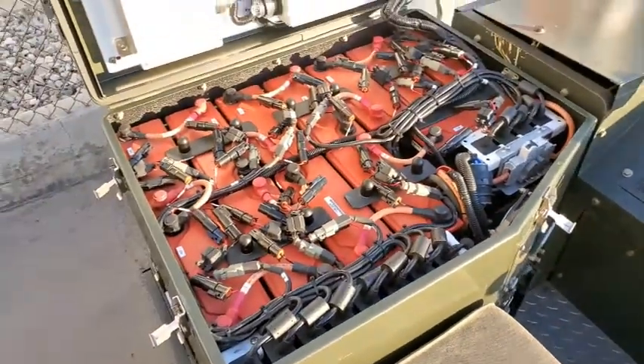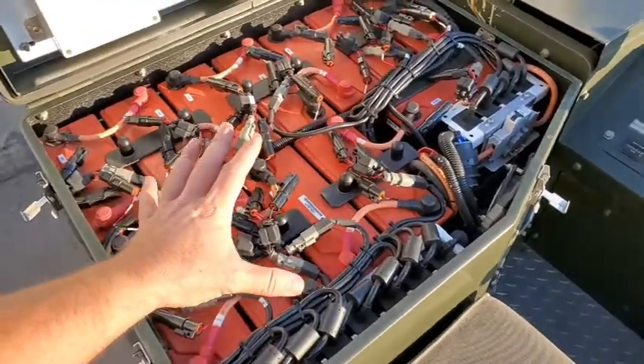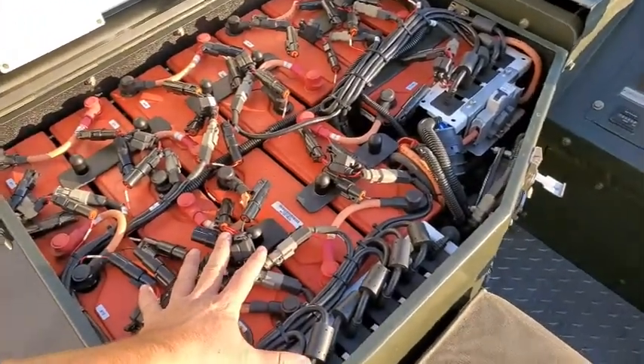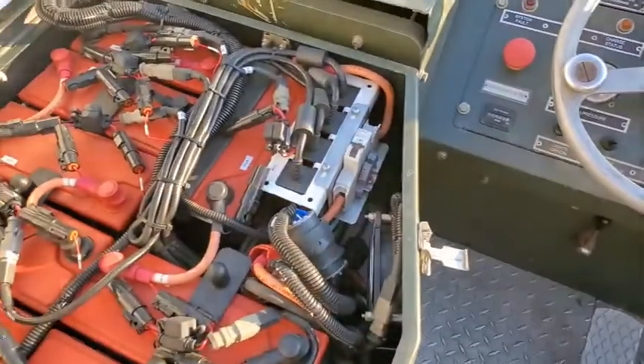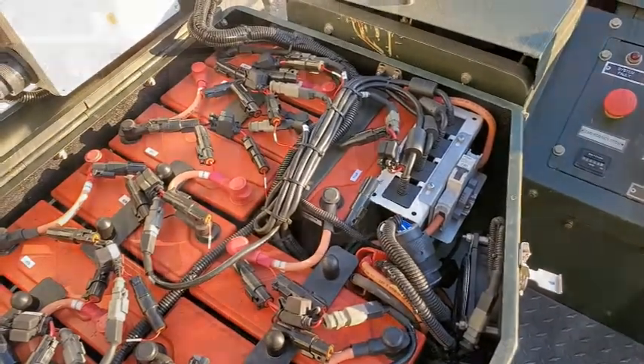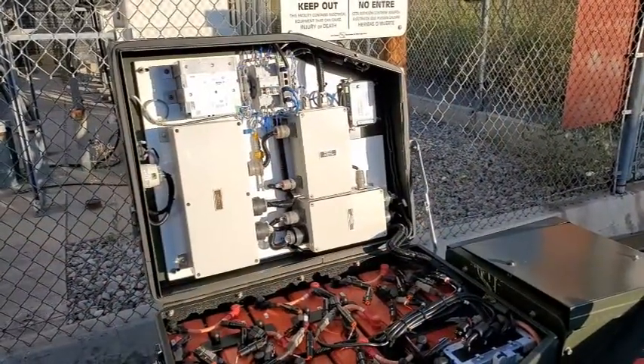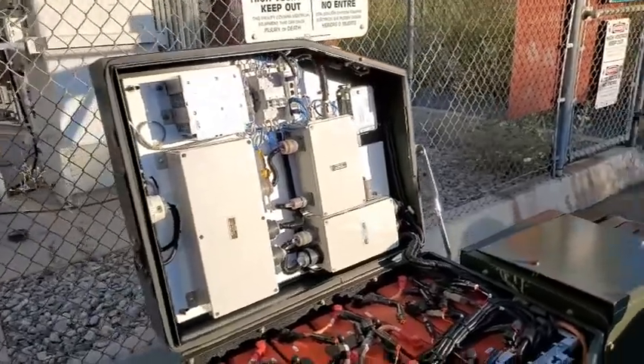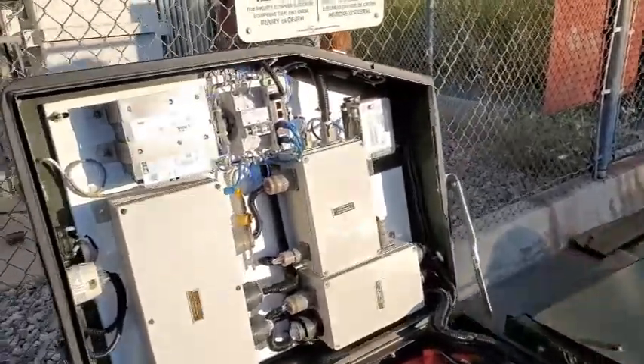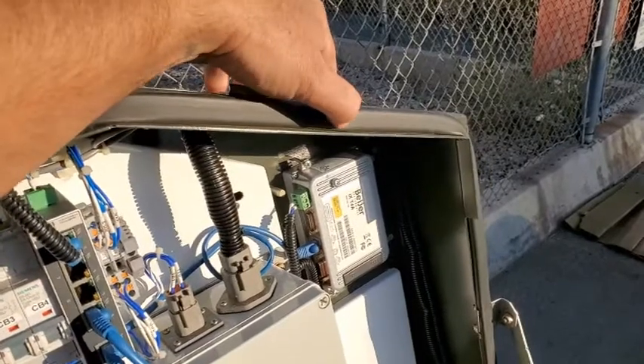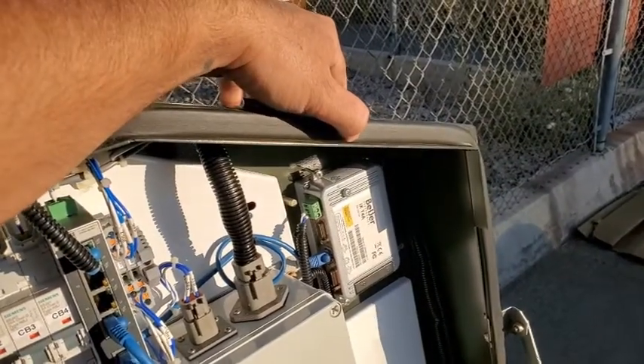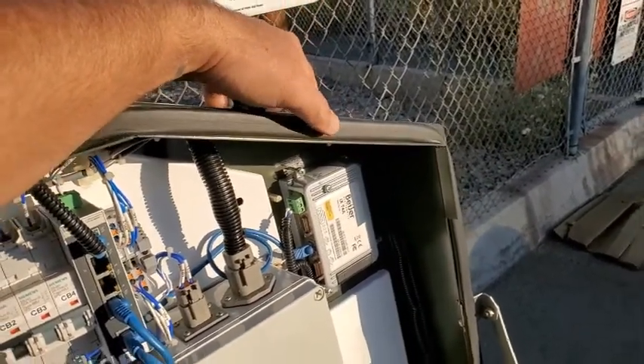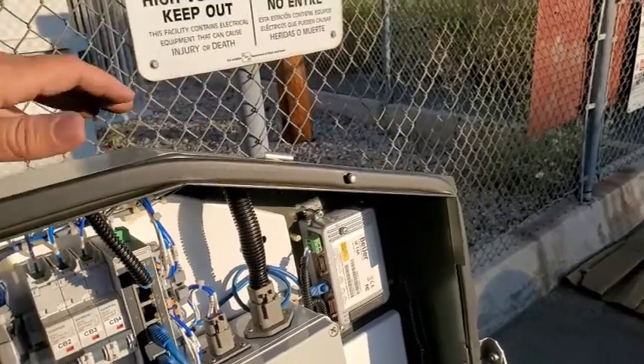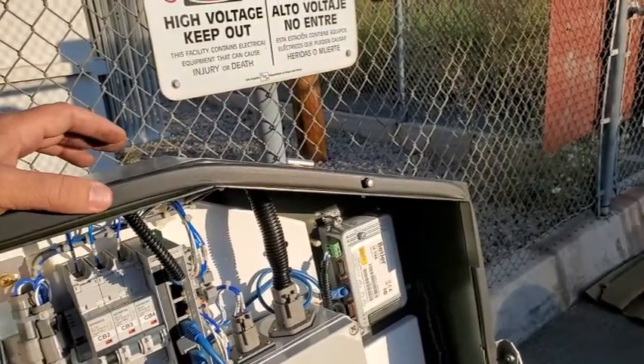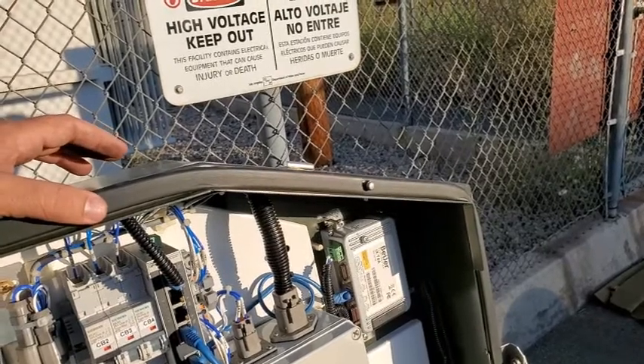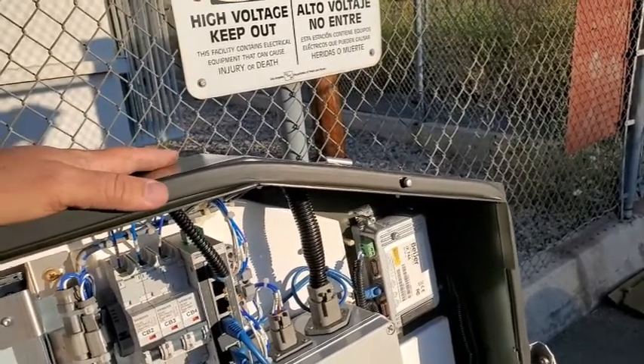If we were to separate the upper and lower halves, the lower half would look just like this, minus CB1. With the battery pack open like this, you will not be able to start the unit due to this switch right here. This switch must be depressed in order to turn on the unit. Now once you've got the HMI on, there is a button in the program that will allow you to bypass that switch and open this for power on troubleshooting.